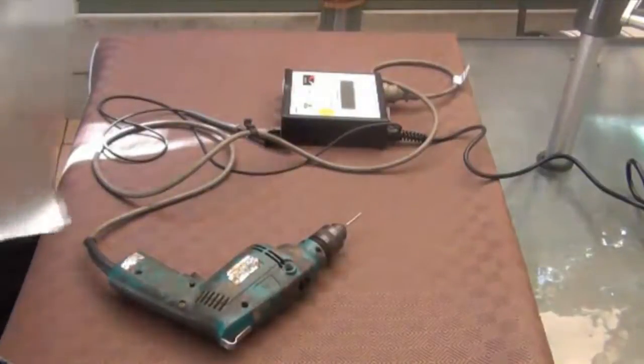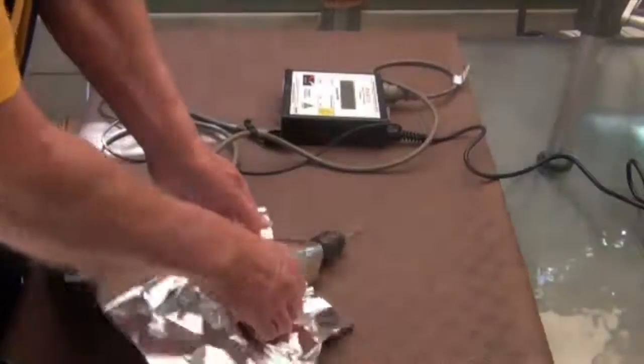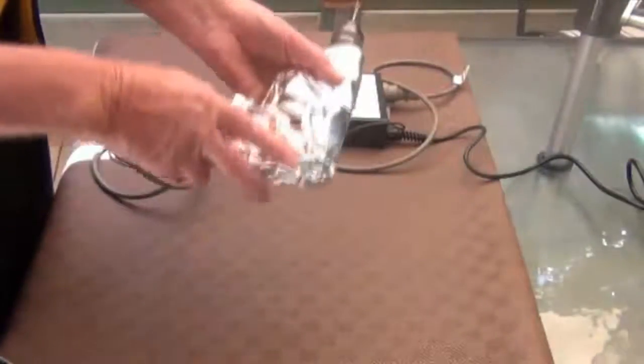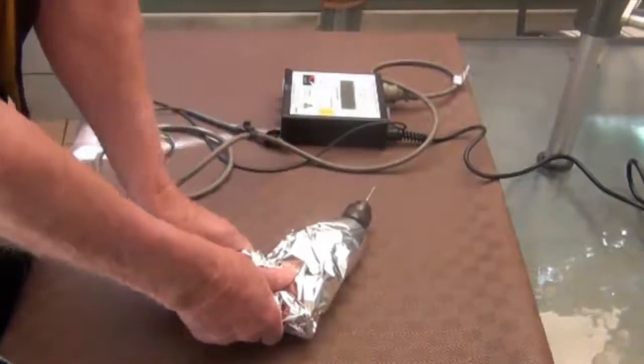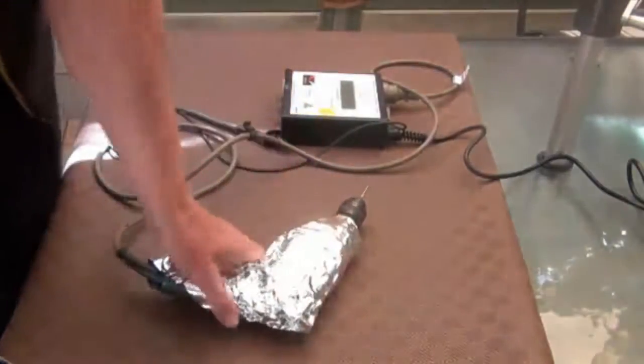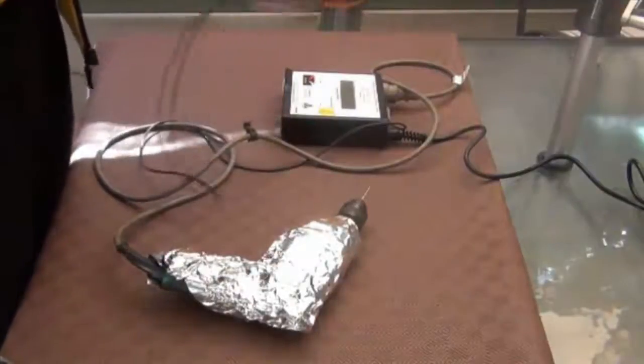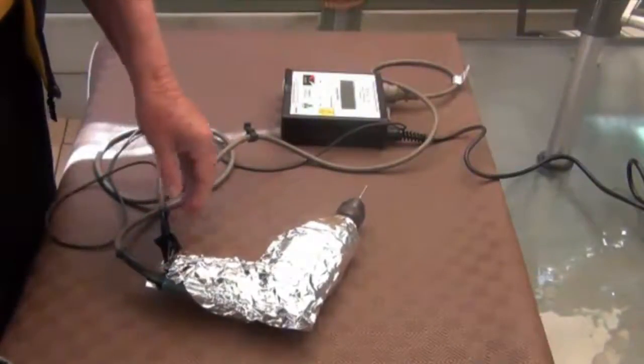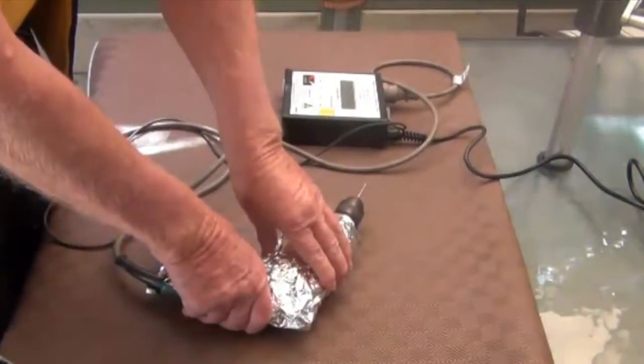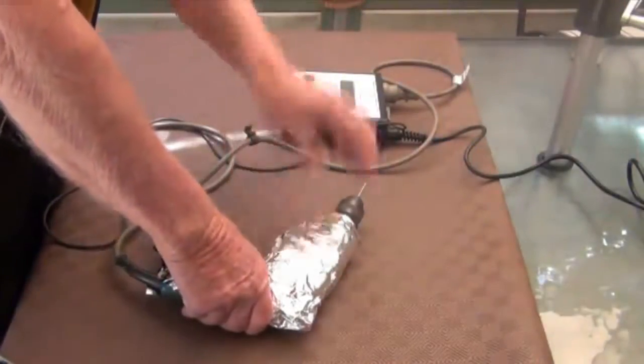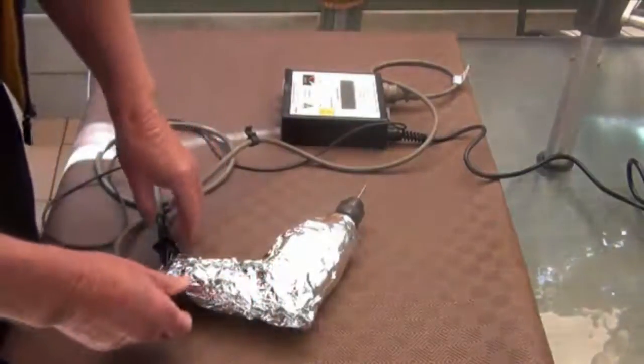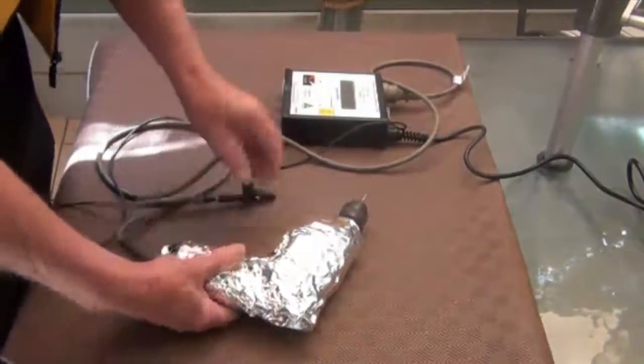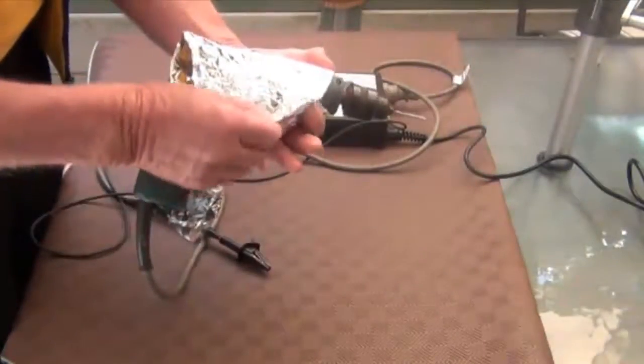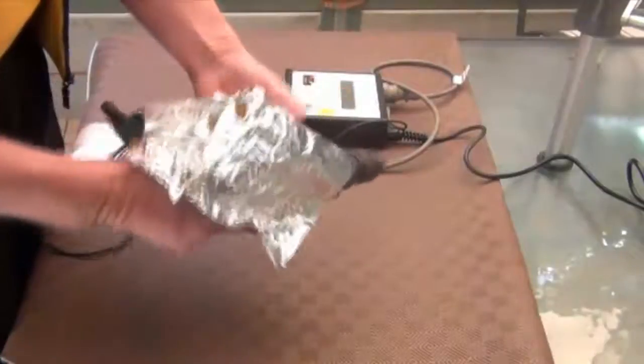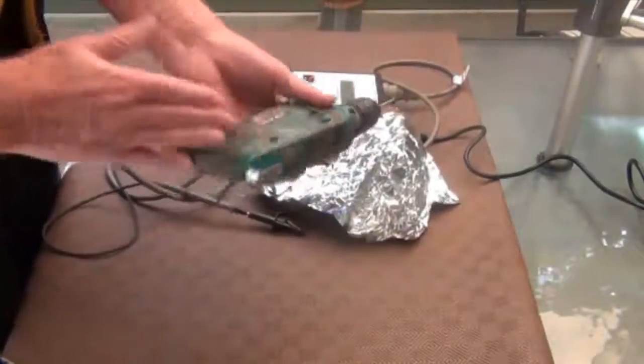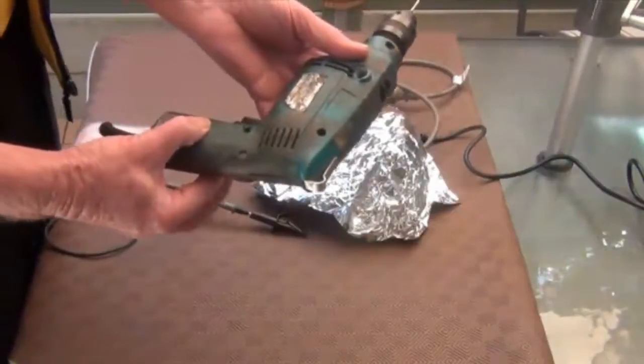I prefer to wrap aluminium foil around. Aluminium foil is better because, as you can see, you can mould it very closely. You then connect your probe onto the aluminium and run the drill. And look for any earth leakage. What this test will do is pick up if there's any cracks in the handle where anything can track through.